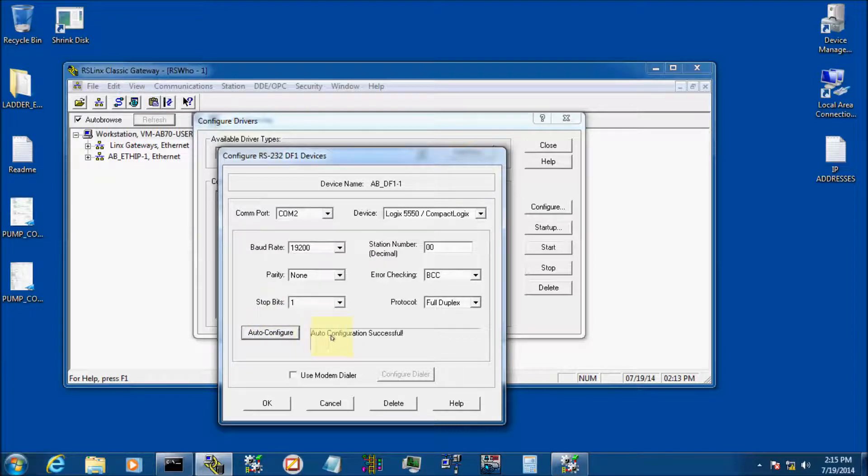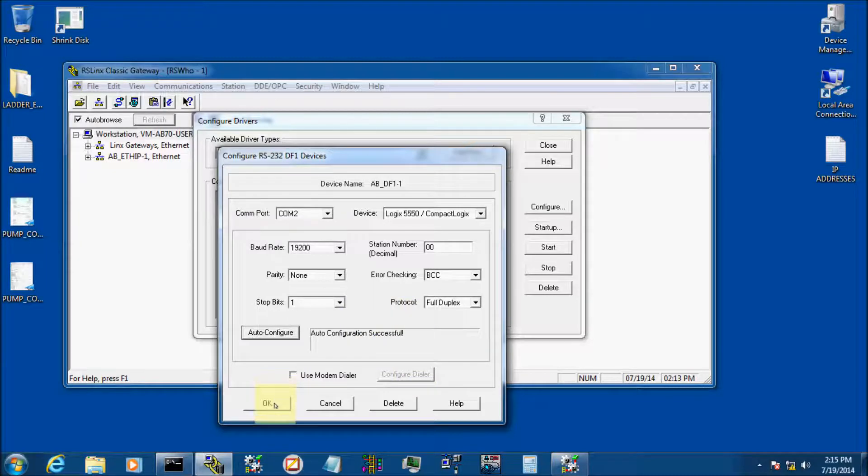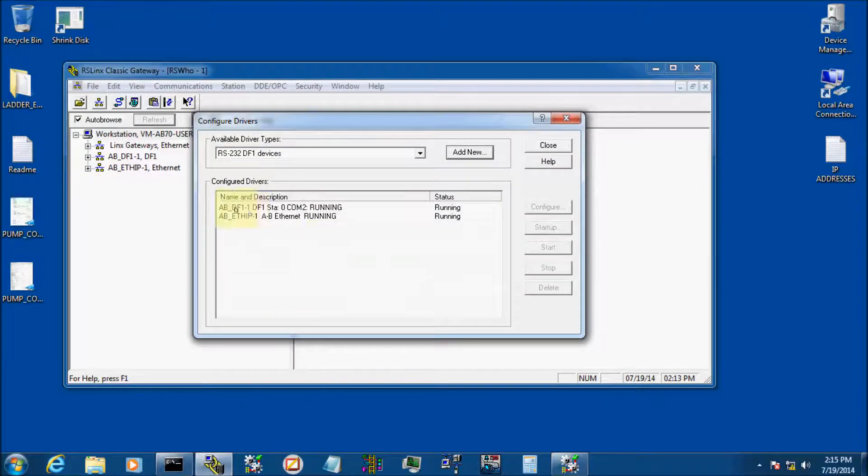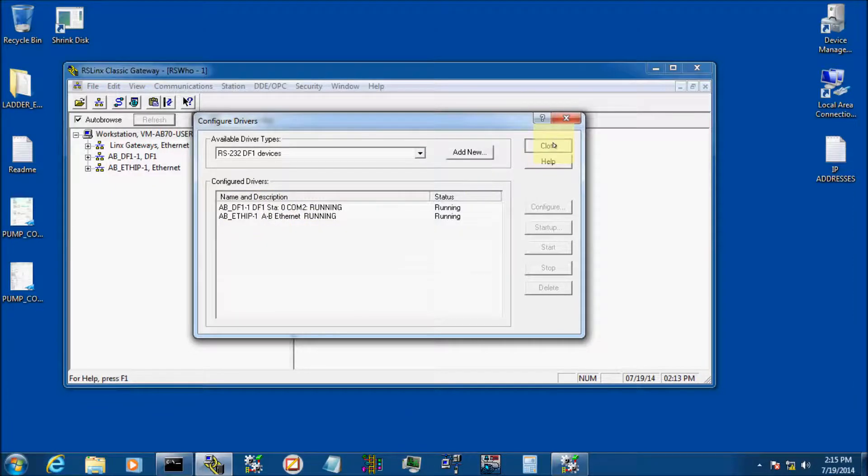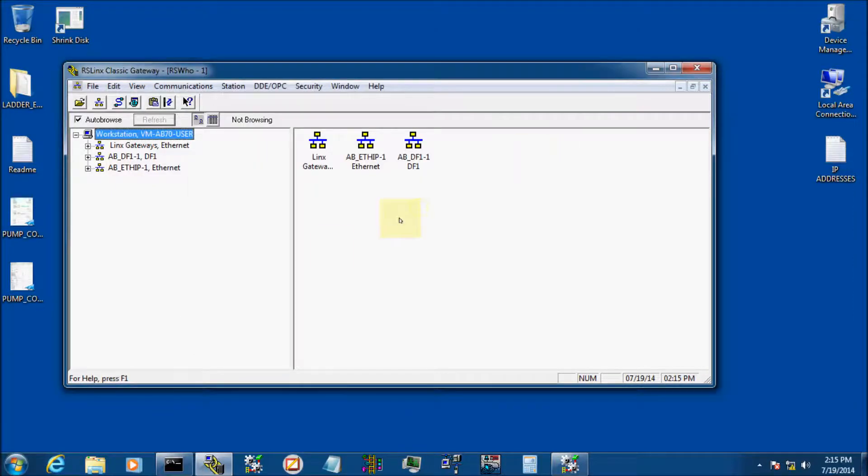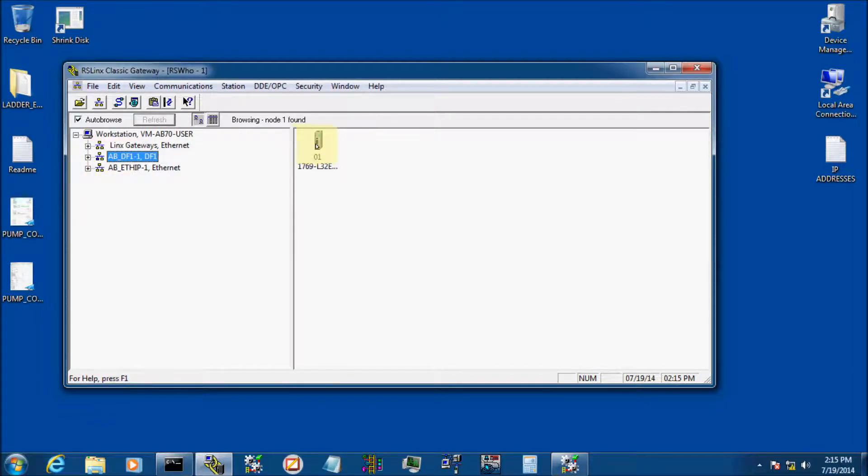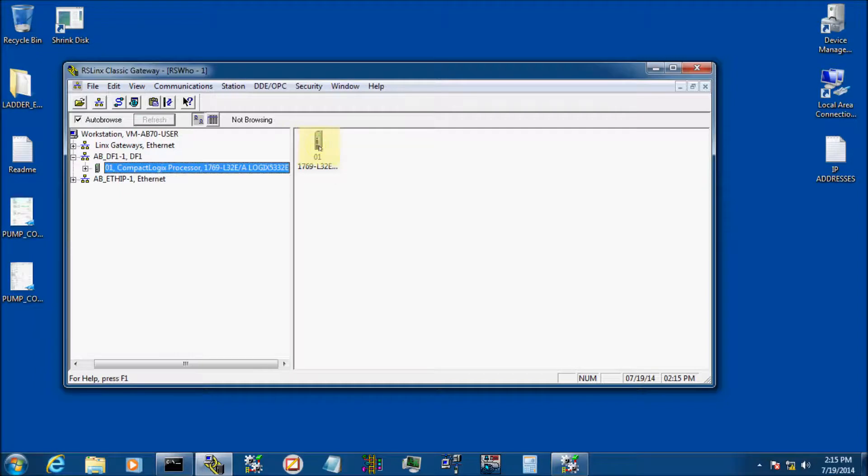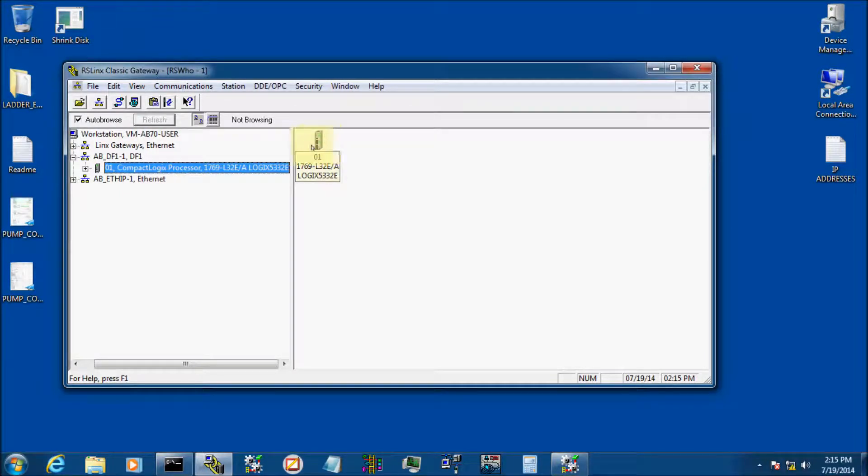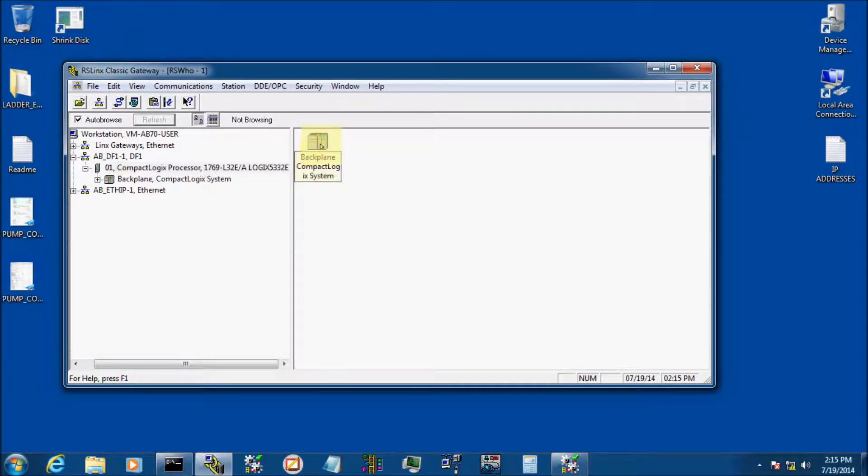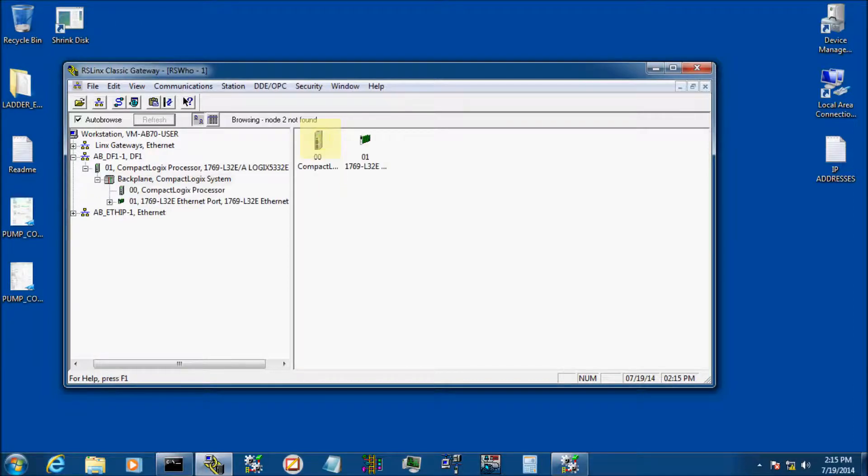Auto Configuration Successful. Now we're just going to click OK. We have our COM 2, our DF1 driver running. We're going to close this window. Now we're going to highlight our ABDF1 driver right here. We can see it's scanning and it's picked up my L32E. We're going to double click on that, double click it again to the back plane, and we'll double click one more time.